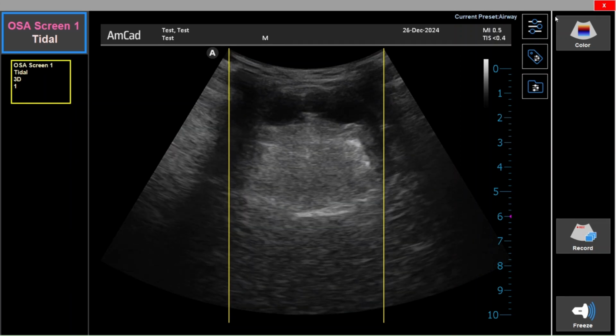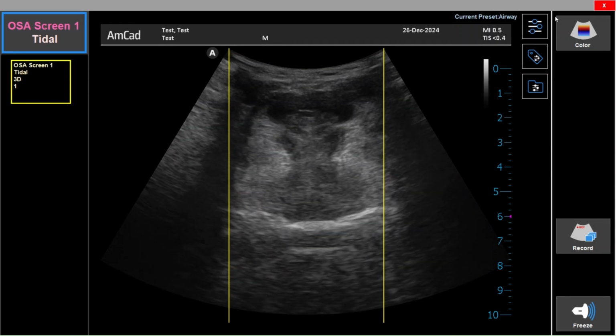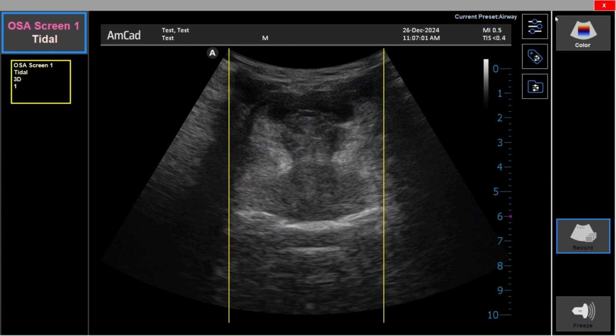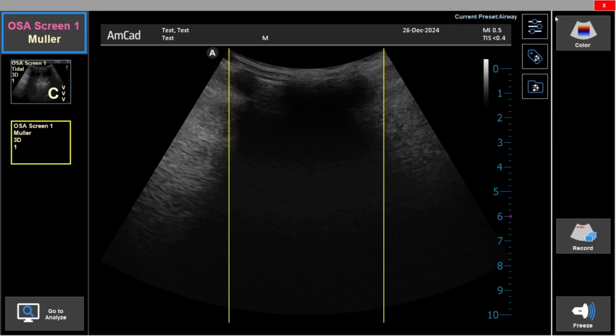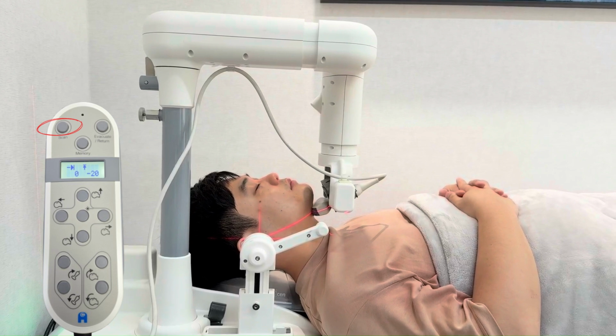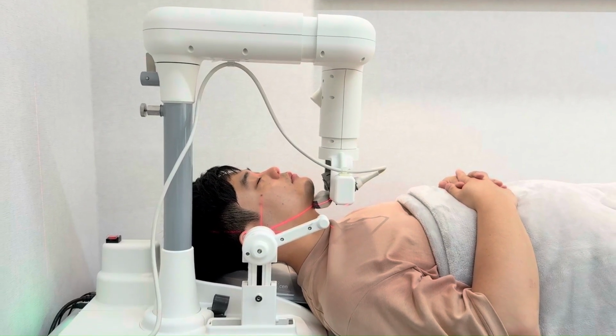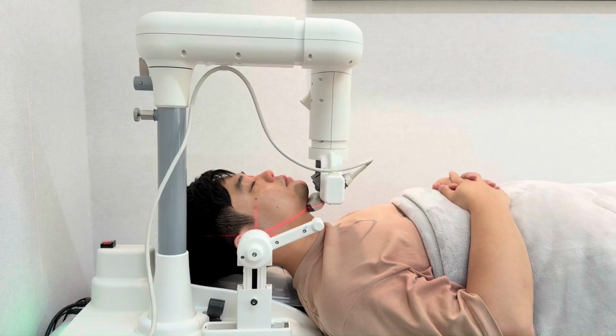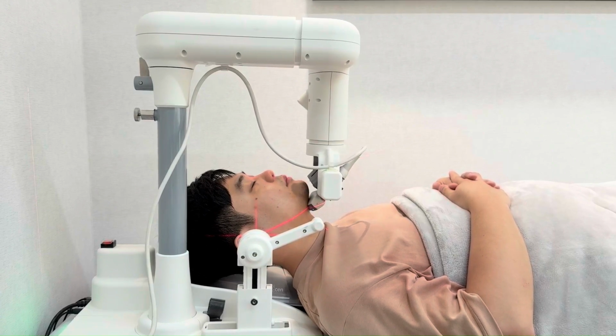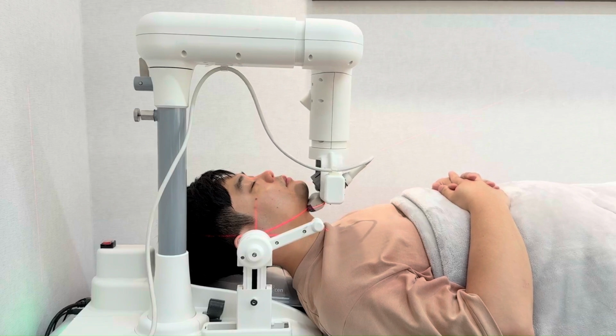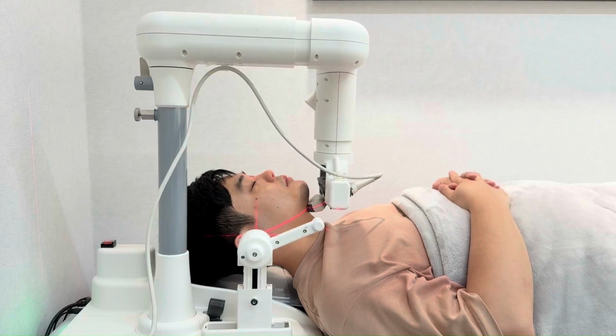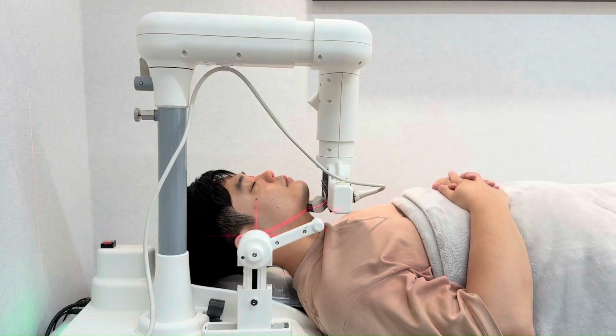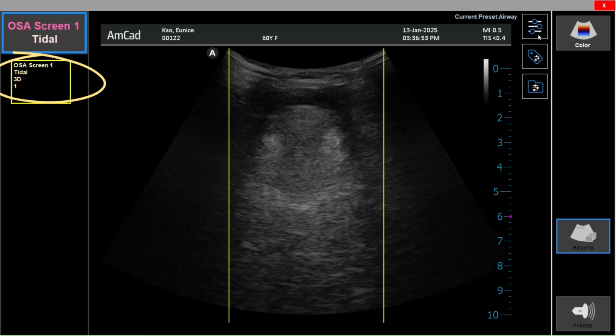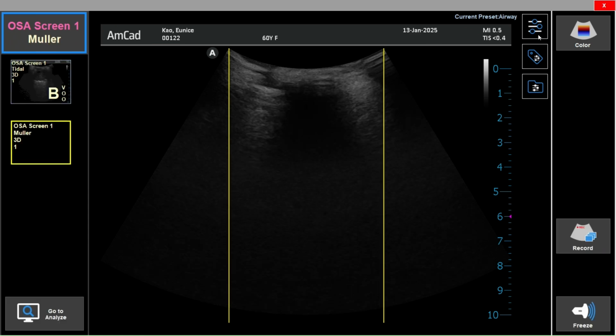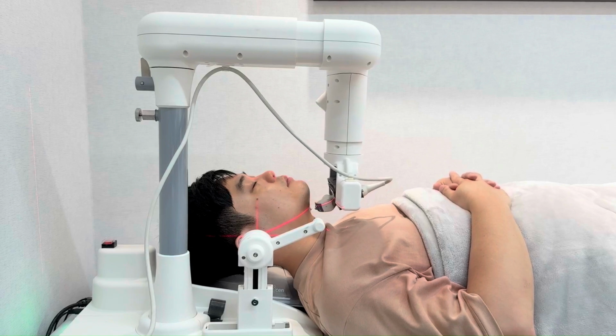Before each scan, check the breathing mode indicator in the top left corner, which displays either tidal mode or Muller mode. Guide your subject accordingly and remind them to avoid talking or swallowing during the 7-second scan. Press Scan button to start. The subject should stay relaxed and breathe normally. The system will beep once to indicate the start. Double beeps signal the completion of one scan. The system automatically saves the scan and returns the probe to the starting position, ready for the next Muller scan.